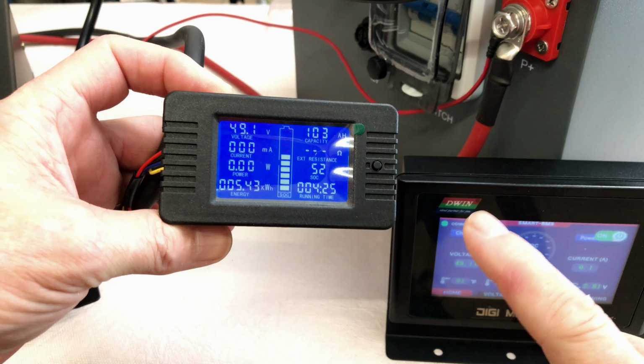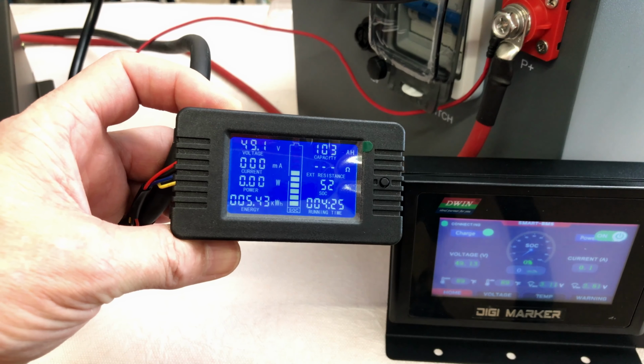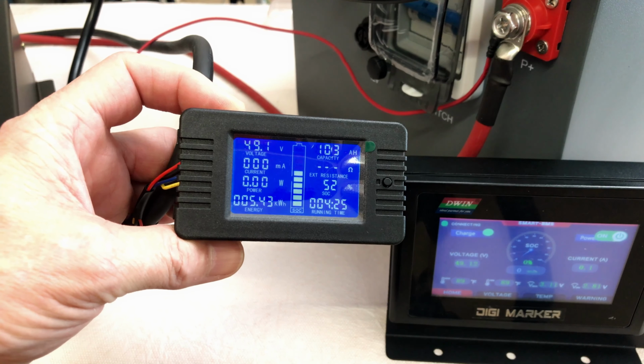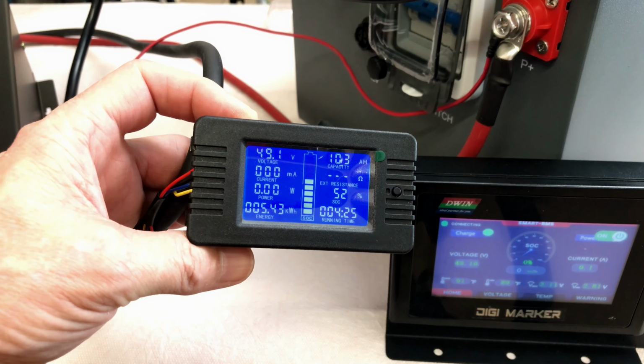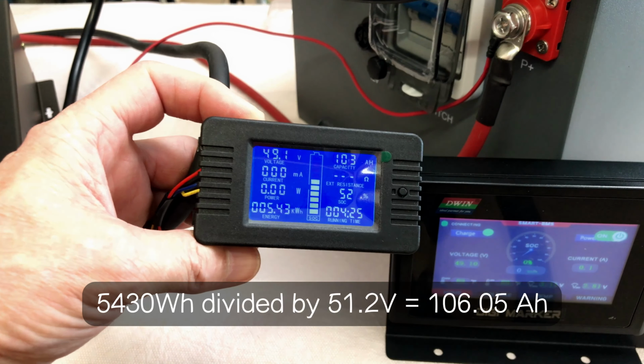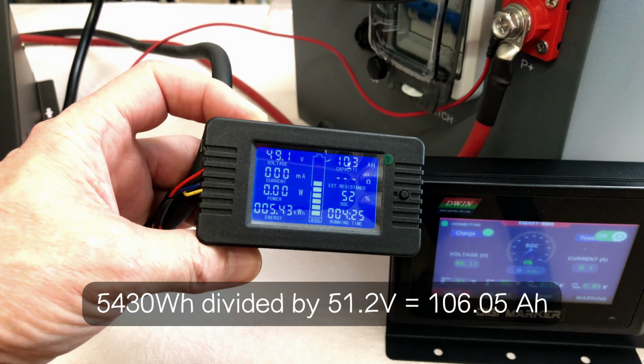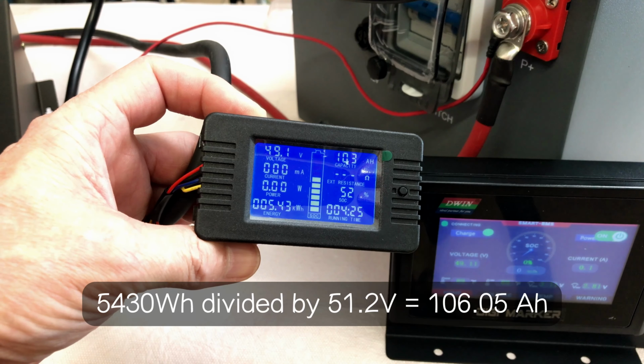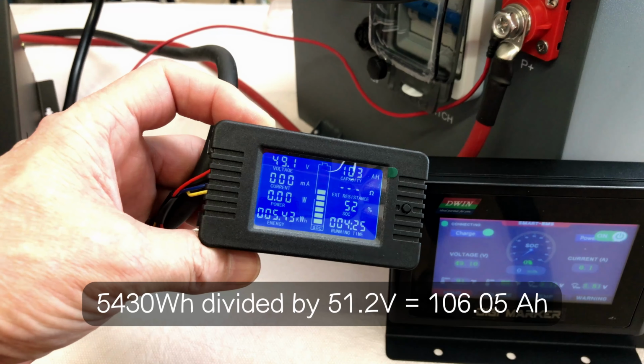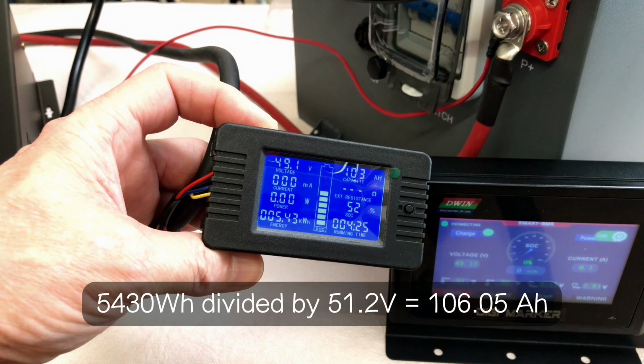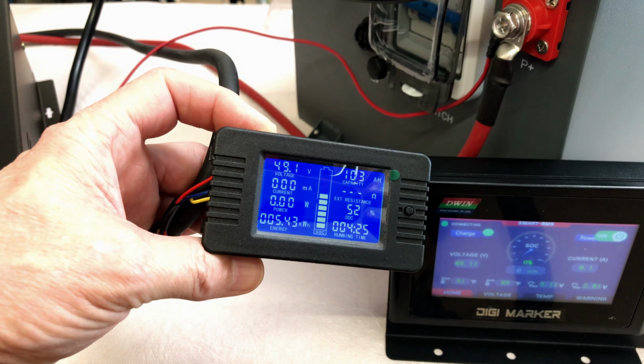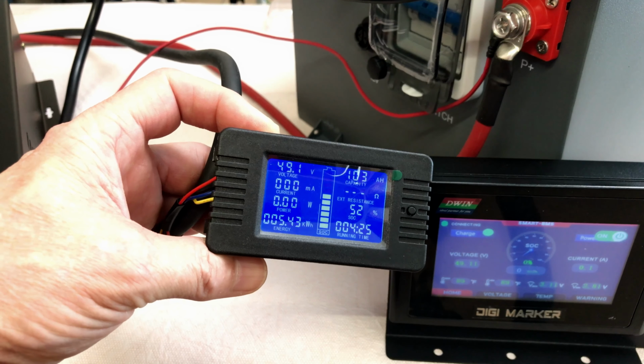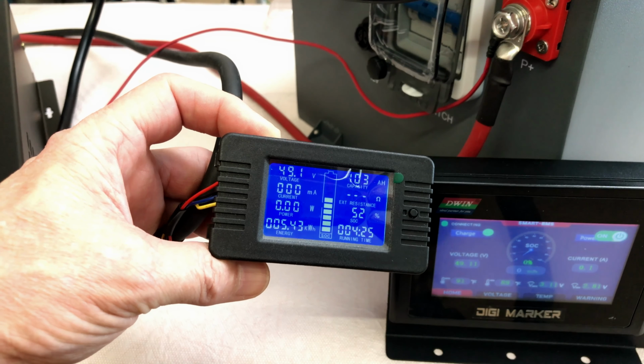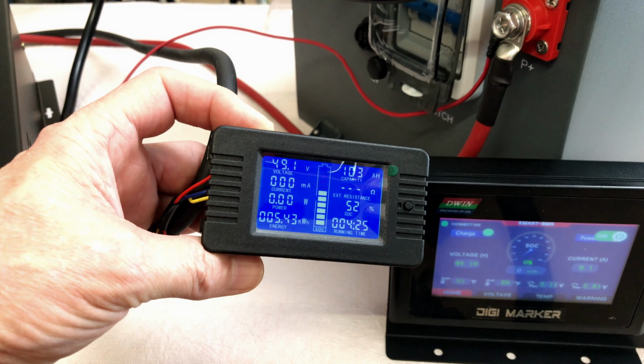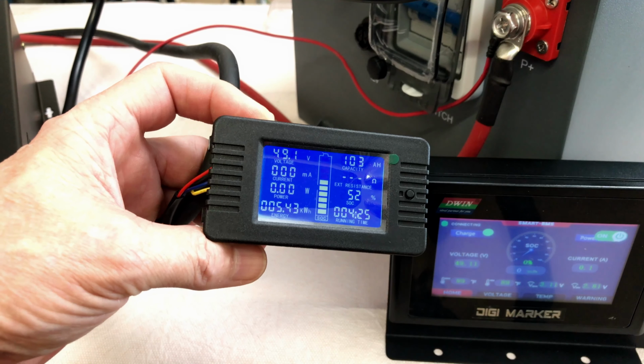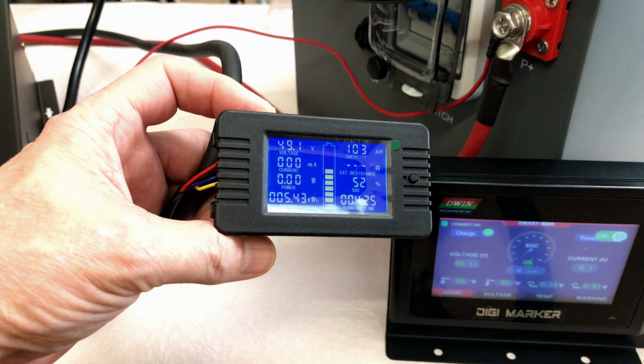You can see we're showing 103 amp hours, 49.1 volts in the upper right hand corner. The test took 4 hours and 25 minutes and 5.43 kilowatt hours, more than the rated capacity. The 103 is 2 amp hours below the 105 rated, and since those 2 amp hours were already on here when I reset the meter, it's exactly 105 amp hours. So it does pass the test as far as its advertised rated capacity of 105 amp hour, 48 volt battery.